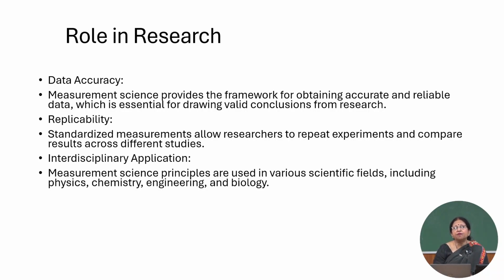Suppose my balance is not calibrated, for example, then what will happen? One time 10 milligram will weigh 10 milligram, another time the same 10 milligram may tend to show less or more. Now this can be very misleading because all my calculations of the rest of the ingredients are based on 10 milligram. So if it is not showing correctly, then all my calculations and eventually my reaction will go bad or will have some shortcoming. So that is the kind of thing that has to be avoided, and therefore the role of measurement science in research is profound.